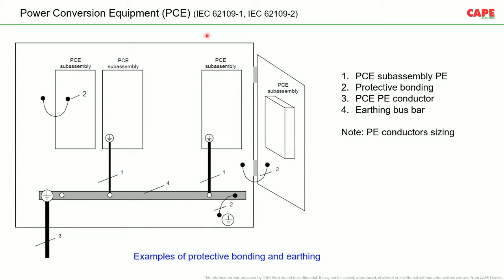The equipment manufacturers, such as the PCE, power conversion equipment manufacturer, make their own earthing arrangement inside the cabinet, including protective earthing, protective bonding, and so on. Say, for example, in this particular picture, they have an earth terminal or an earth bus bar. Number 3 is the incoming PE conductor. This incoming PE conductor is coming from the main distribution board or the main earth bus bar of your installation. Then internally, you see here the earthings are made. So the manufacturer has already taken care of his earthing, provided the earth terminal of the power conversion equipment is connected to the incoming earth bus bar. This incoming earth wire is the wire which comes along with the phase and the neutral of the incoming power supply. So basically, for the inverter as such, an earth pit is not required. You are supposed to connect to the incoming earth wire.